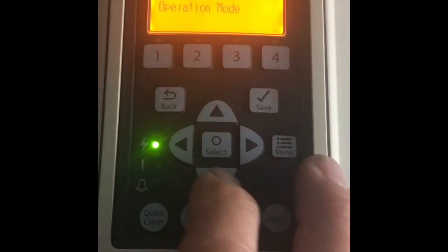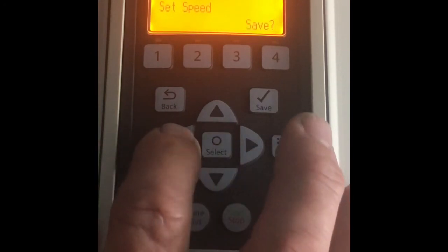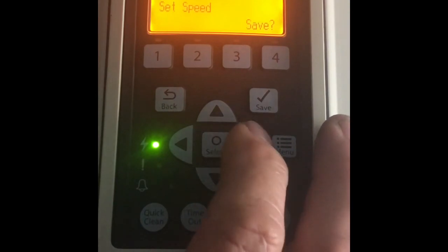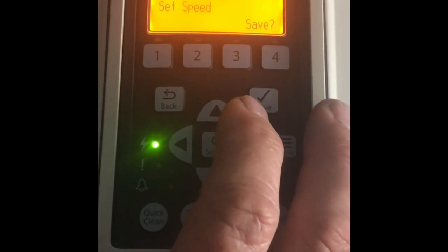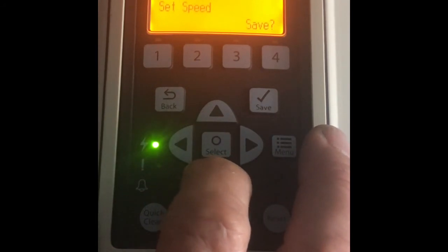Hit save. Go down. There's where our speed is going to come into play. So under normal circumstances, you can usually set up a pool, a straight pool, nothing, no features, nothing like that, for about 1500 RPM. And I'll show you the time that we're going to do for that as well.